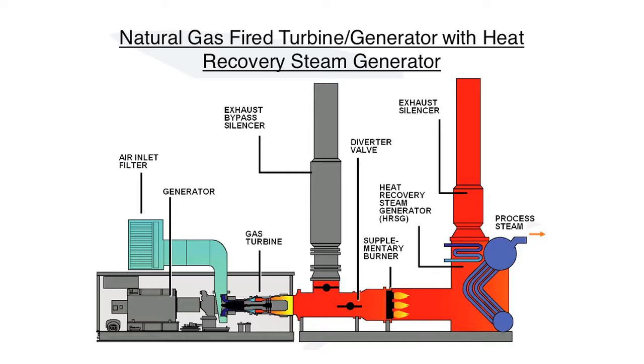Well, what we do at Eight Flags, it's similar to combined cycle, but it's different. We have the gas turbine, a smaller industrial gas turbine, just over 20 megawatts. The gas comes in, fires the turbine, creates power, which goes back to the substation, which then gets pushed back to the grid. And then throughout the combustion process, the turbine creates heat. Heat goes through the boiler, heats up the drum, creates steam, which goes back and supplies steam to the paper mill. They're using that heat in the steam to dry the paper in the process, so we're not throwing any heat away from that.